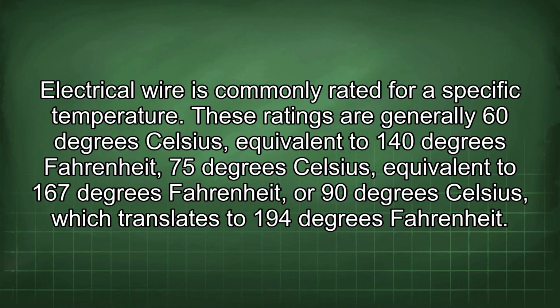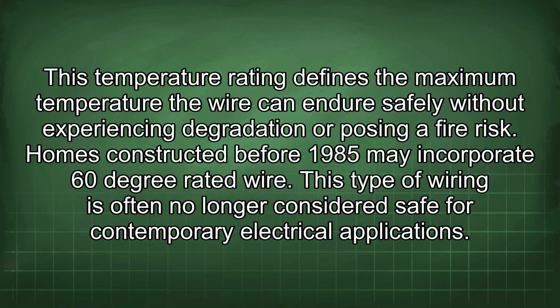Electrical wire is commonly rated for a specific temperature. These ratings are generally 60 degrees Celsius, equivalent to 140 degrees Fahrenheit, 75 degrees Celsius, equivalent to 167 degrees Fahrenheit, or 90 degrees Celsius, which translates to 194 degrees Fahrenheit. This temperature rating defines the maximum temperature the wire can endure safely without experiencing degradation or posing a fire risk.